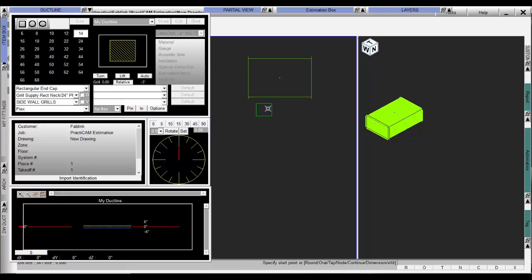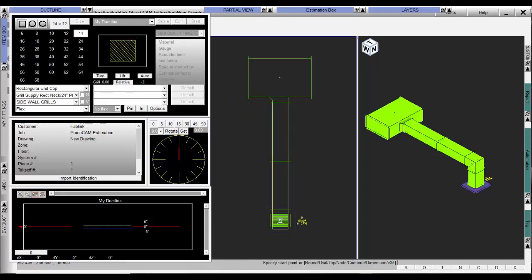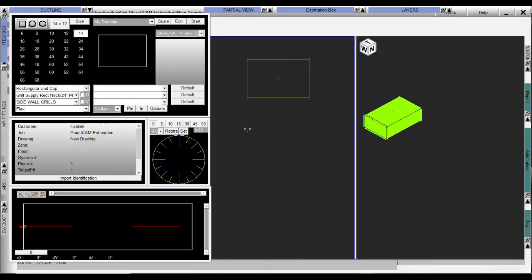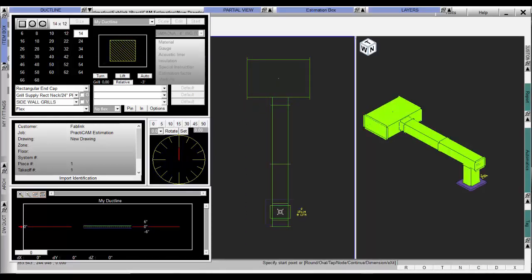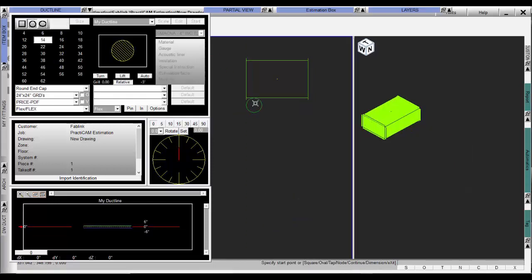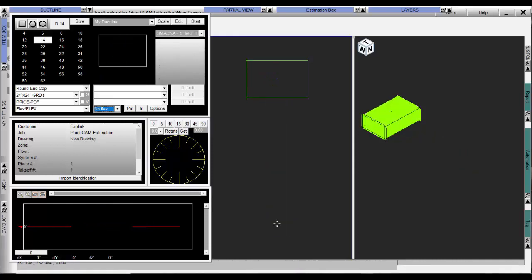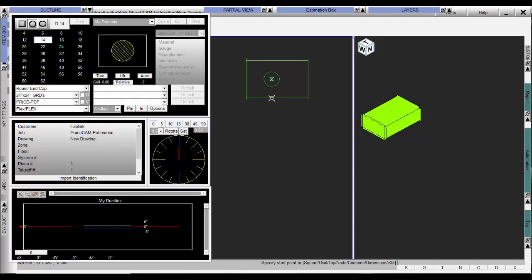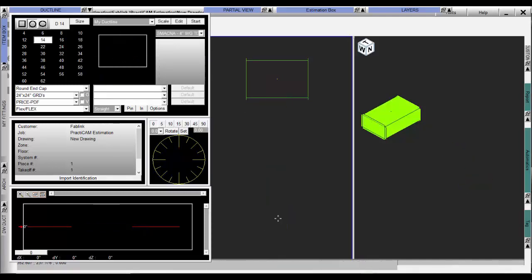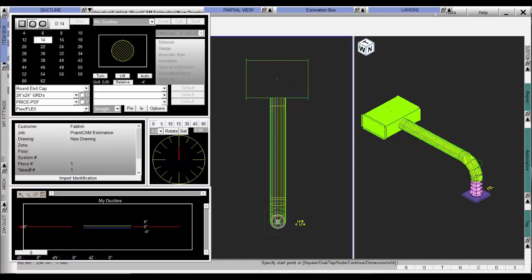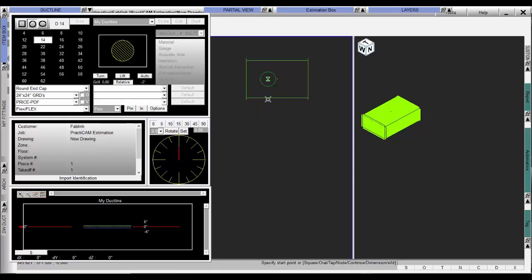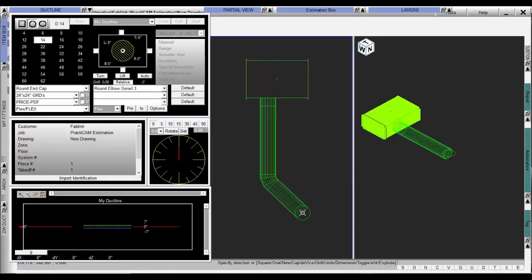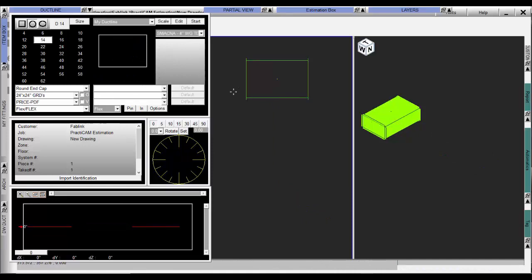One of the fastest features in duct line is the grill routing option. See here as we route about a dozen different routes that are all automatic using the G for grill command. First was a rec tap to rec grill using an elbow. Next was a rec tap to rec grill, but this time with the collar underneath and an end cap on the line. In addition to these, there's an ever evolving range of different combinations based on user preferences including, but not limited to, parameters for min max flex, absolute and relative elevation parameters for perfect or estimated grill placement, ability to route with only hard pipe, ability to use any combination of pipe elbow and flex you wish. If engineers allow you to bend flex off the edge of pipe, there's a route for that. If elbows are needed first and flex isn't allowed to bend, there's a route for that.